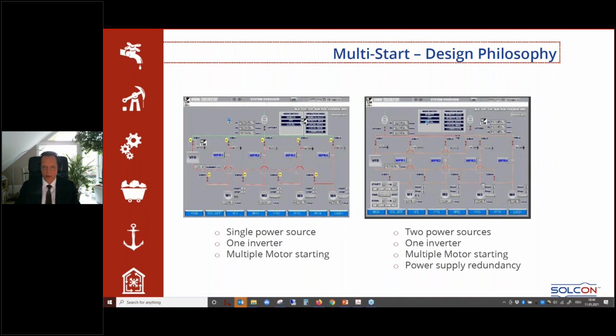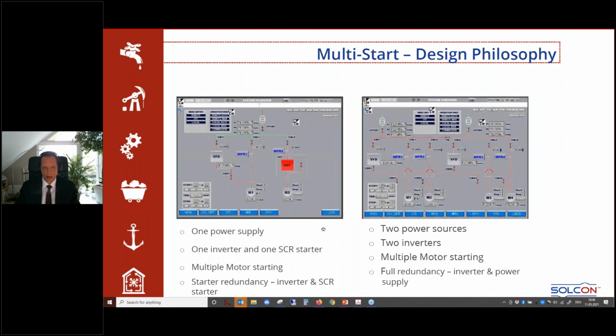Also possible with our predefined topologies when it comes to multi-start. Here you have one power supply, one inverter, and one SCR starter, also possible with our control module. Sometimes you have starter redundancy, inverter and SCR, also possible. Two power sources, two inverters, that's what I said before, multiple motors starting, full redundancy, inverter and power supply with the highest availability, if and when needed and asked for.